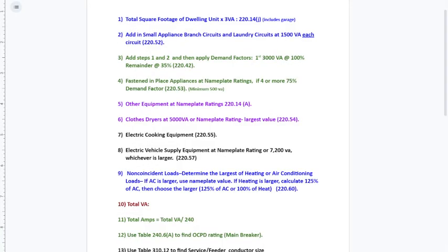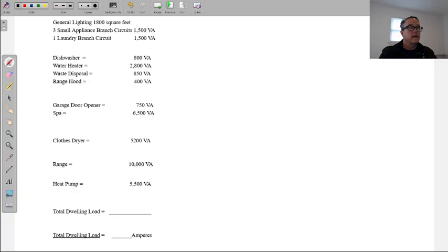It comes out of Article 220.14(A), which says anything else that doesn't fall under general lighting loads, doesn't fall under appliances, isn't a dryer, isn't an oven, isn't part of the air conditioning system, isn't an EV, everything else will be at the nameplate rating of the equipment. We can drop back there for a second and pick that up.